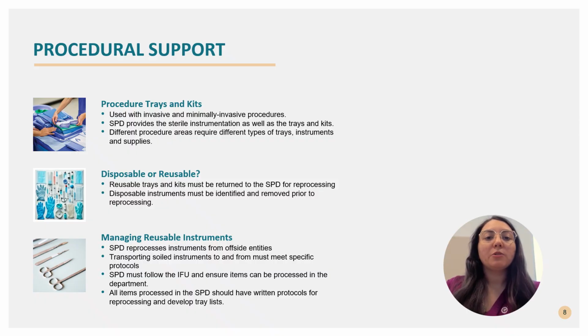The sterile processing department reprocesses instruments for both ancillary departments and off-site entities. Transporting soiled items must meet biohazard transport and infection prevention guidelines, and the return of clean instruments must follow the sterile transport protocols. For all items bought, the sterile processing department must be provided the manufacturer's written instructions for use and ensure the items can be processed in the department. All items processed in the sterile processing department should have written protocols for reprocessing and developed tray lists.